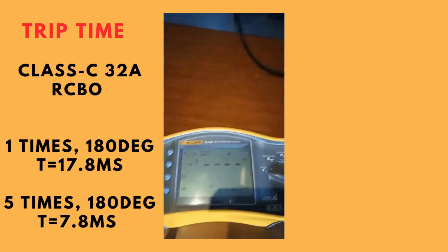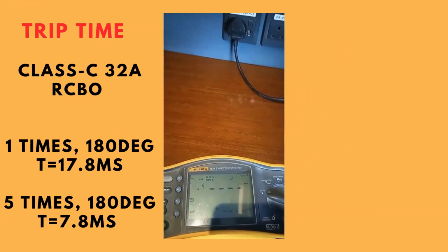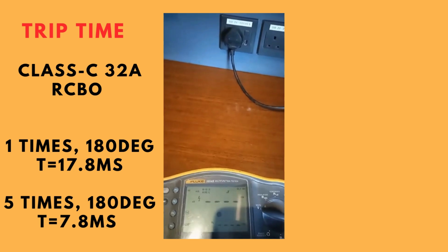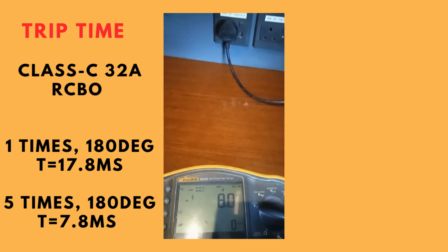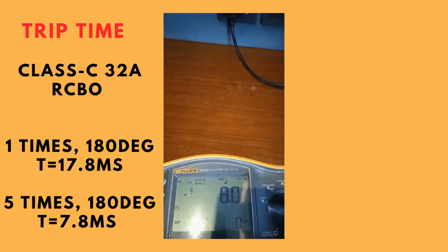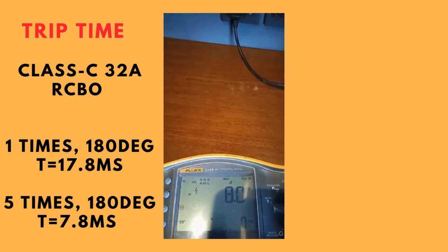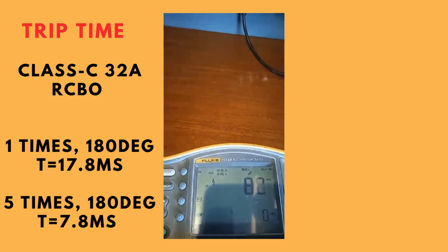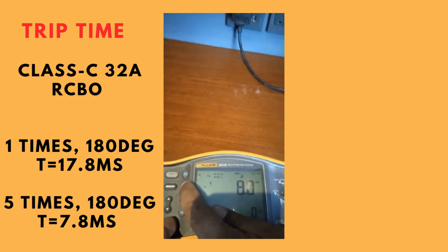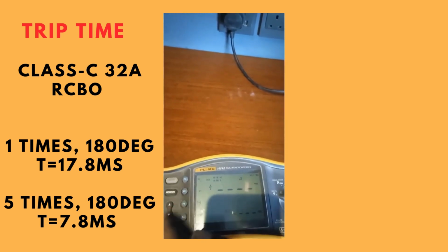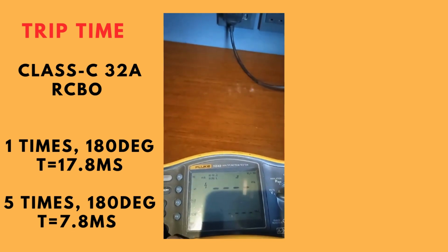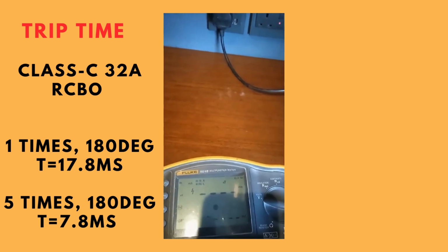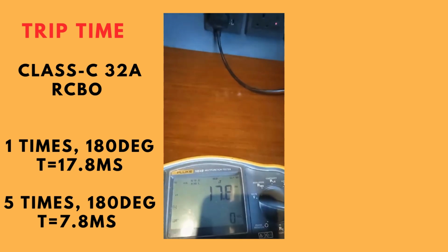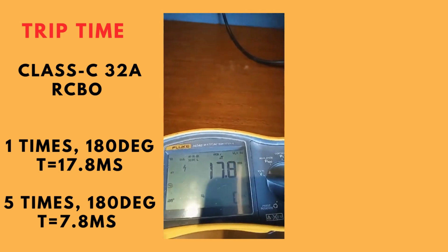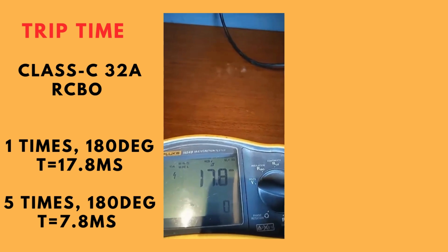Now we look at the time it takes to trip, and then we move back to the DB side and see if it trips. Now it trips at 8.0 milliseconds at times 5. I think you should start at times 1. Okay. Now we move to times 1. Reset. Put it back on. Okay. Now it trips at 17.8 milliseconds.